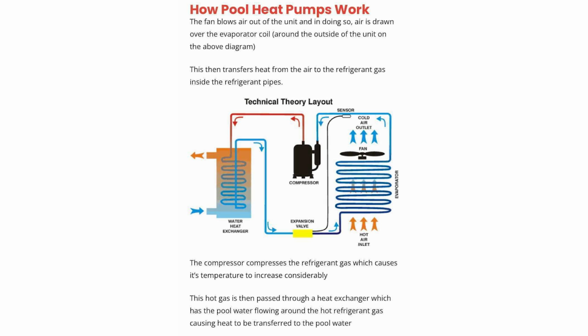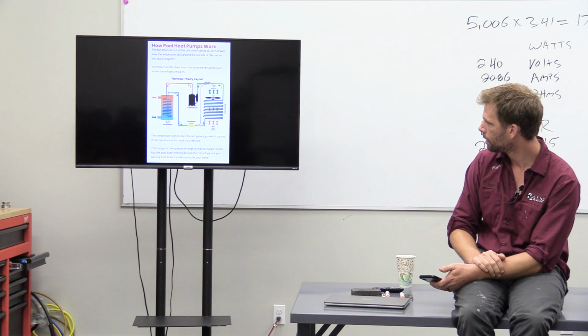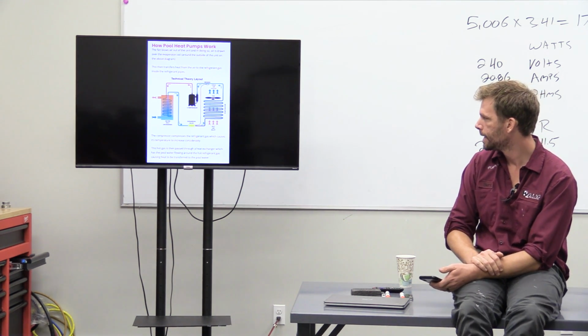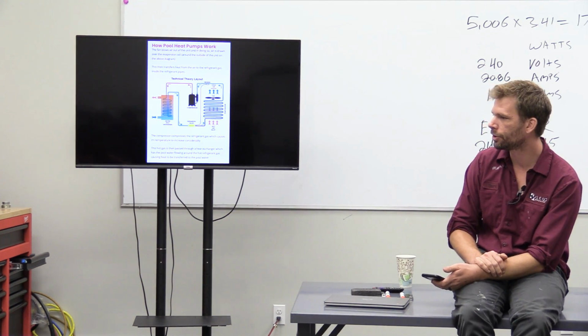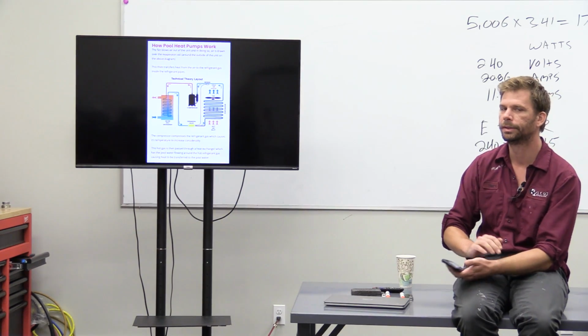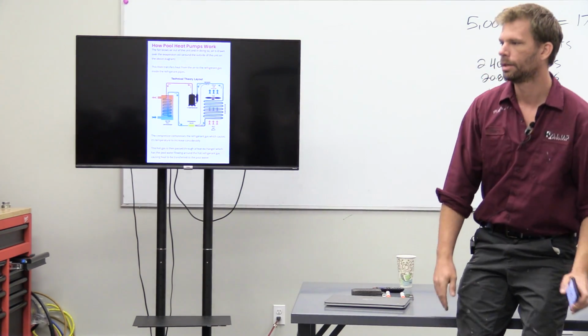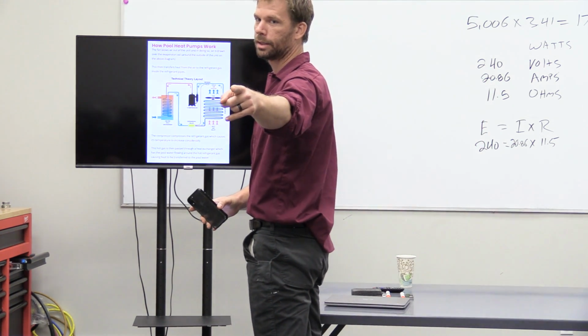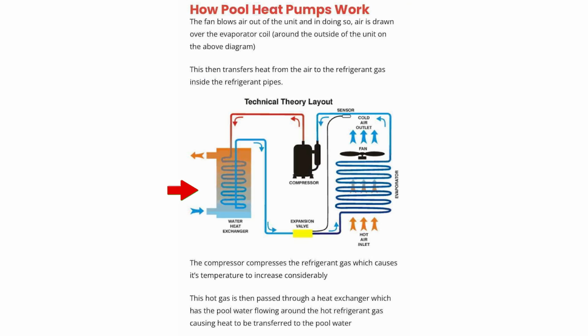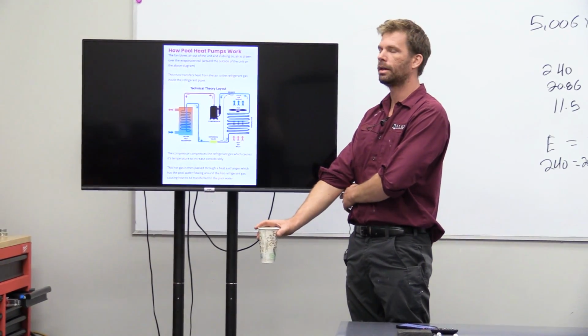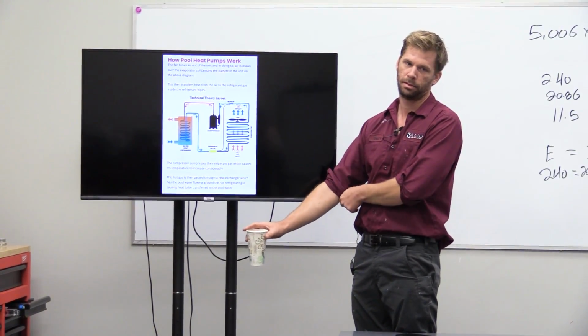Where is the condenser? Wrong. Nope. The condenser. What is the function of the condenser in a refrigerant circuit? It rejects heat, condenses what? Refrigerant. Yep, it is on the left. So on a pool heater, we're using water to condense our refrigerant. So our outdoor condenser fan is on top of our evaporator, which is the coils outside. And so basically an AC heat pump running in heat mode is your pool heater.